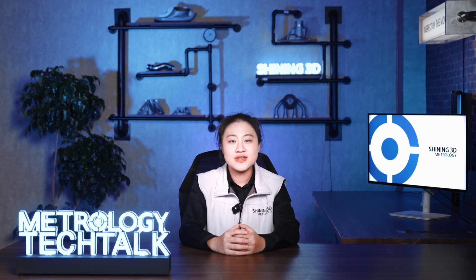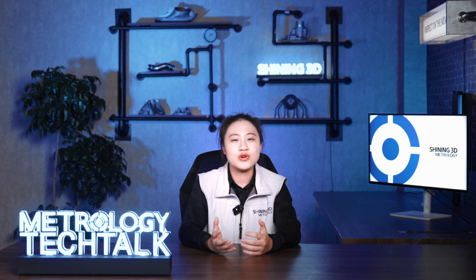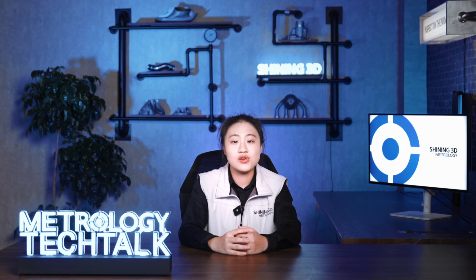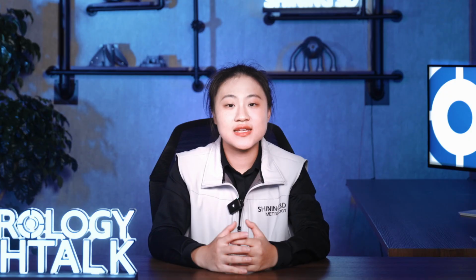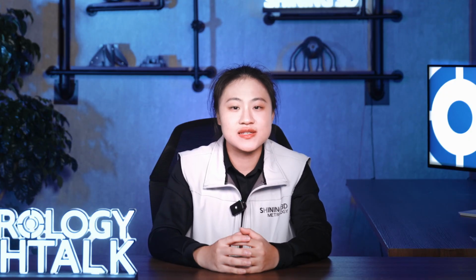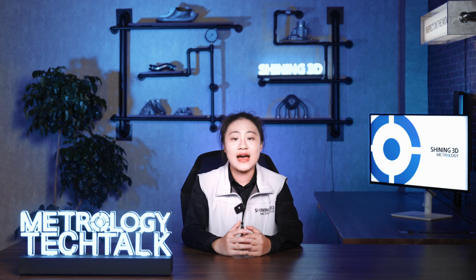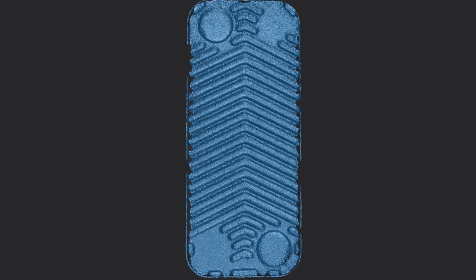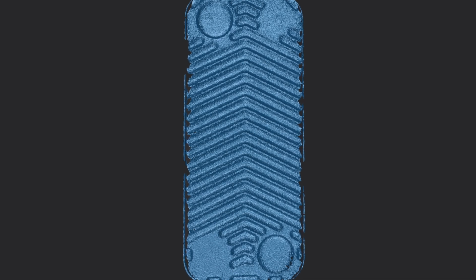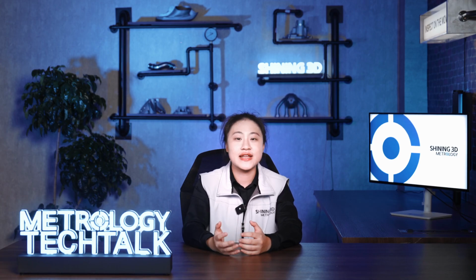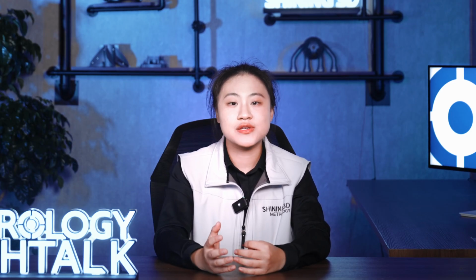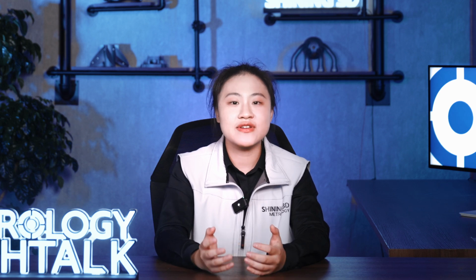Alright, so the room is in a stable temperature. But what if the floor is shaking? Vibration is also one of the biggest enemies. A 3D scanner is essentially a highly advanced camera system. Just like taking photos on your phone with shaky hands, the images will be blurry. During a 3D scan, heavy vibrations will also blur the raw 2D frames. As a result, the software generates noisy and lower quality data. To avoid this, try to isolate your setup on a vibration-free workbench. If that is not possible, use reference markers so the scanner can dynamically track the part even if there's movement.